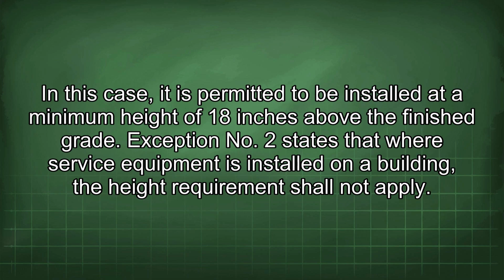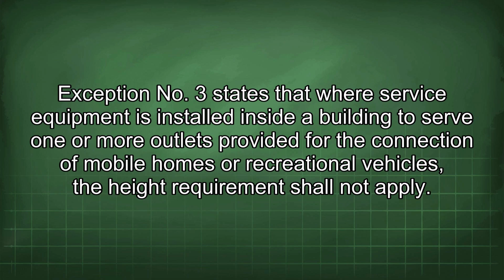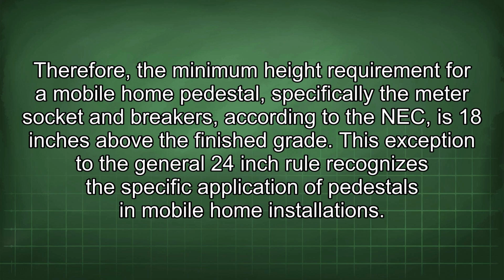Exception No. 2 states that where service equipment is installed on a building, the height requirement shall not apply. Exception No. 3 states that where service equipment is installed inside a building to serve one or more outlets provided for the connection of mobile homes or recreational vehicles, the height requirement shall not apply. Therefore, the minimum height requirement for a mobile home pedestal, specifically the meter socket and breakers according to the NEC, is 18 inches above the finished grade. This exception to the general 24-inch rule recognizes the specific application of pedestals in mobile home installations.